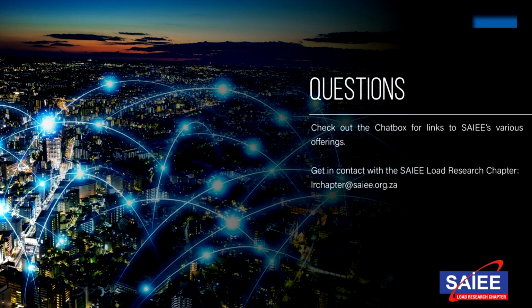Mike, that's quite a mouthful, you care to comment? Yeah, so certainly 1547 does look at power factor. Under reactive power and voltage control, they do make allowance for constant power factor control mode, where you set a configurable power factor set point. So it does tackle that as one of the modes, along with volt-var and watt-var. You do have a power factor control mode. I hope that answers the question.